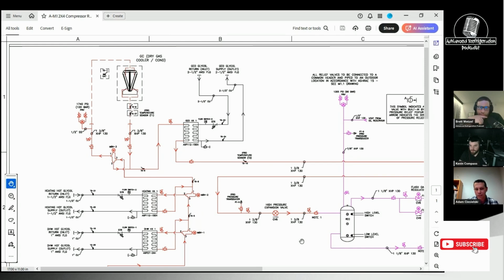Gotcha. And the coils have to be rated for 90 bar. So from a supermarket perspective, they're not there yet. So they're only 650. So you're really limited to defrosting at 525 psi-ish. And you're basically barely above freezing at that point, because 36 degrees is about 520. So you're not much greater than that. Or you're not really getting that much heat out of it, right? Yep.